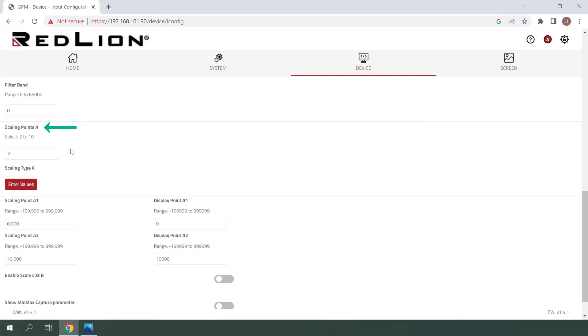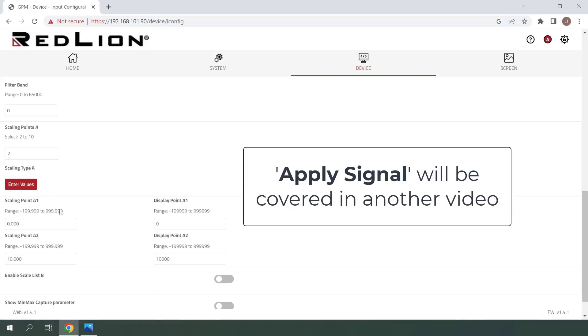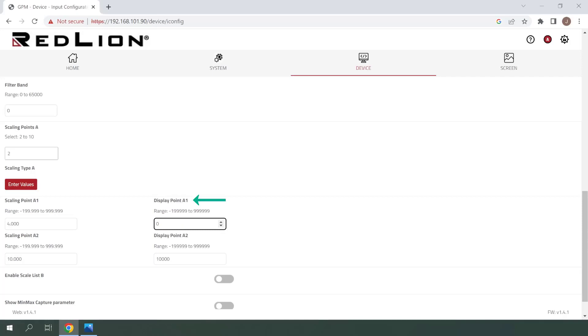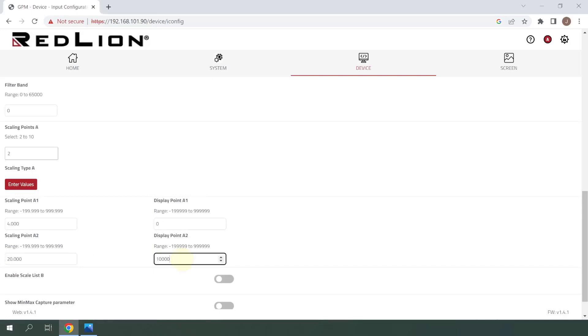Next up, we have scaling points A, which is the number of scaling points for list A. Our 4 to 20 milliamp signal will be linearly scaled from 0 to 100, so 2 scaling points is enough. If needed, we could have up to 10 scaling points for a nonlinear scale. For scaling type A, this will be left at enter values, which is the only option from the web server. Note that from the unit itself, you'll have the option to apply signal rather than enter the values. Scaling point A1 will be the low end of our input signal, which is 4 milliamps — I'll enter a value of 4 here. Display point A1 will be 0, because 4 milliamps will represent a value of 0. Scaling point A2 will be the high end of our input signal, which is 20 milliamps — I'll enter a value of 20 here. Display point A2 will be 100, because 20 milliamps will represent a value of 100.